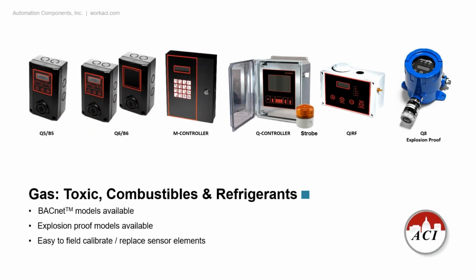This is more of our parking garage style application, the sensors and the controllers that go with them. The Q5 and B5 is the single standalone. The Q6, B6 is that combination CO main, and then NO2 as the remote or any other style of combustible or toxic. The M controller is 32 input, and that offers about, I think, 95% of the applications customers use. The Q controller is the mother load. That's the, I think, 124 different inputs on that guy. And we do have all the strobes and horns that go with these applications that are needed too.